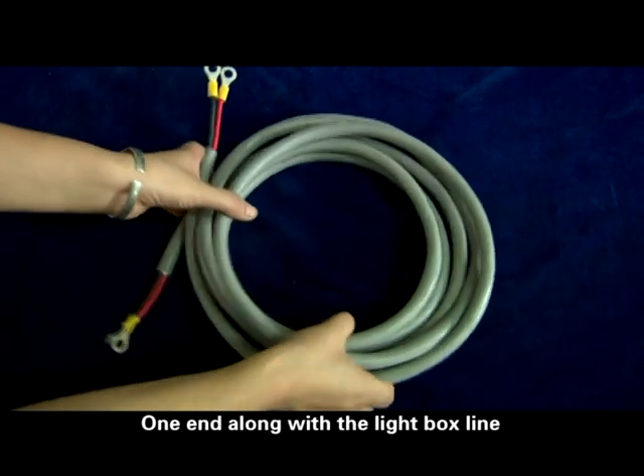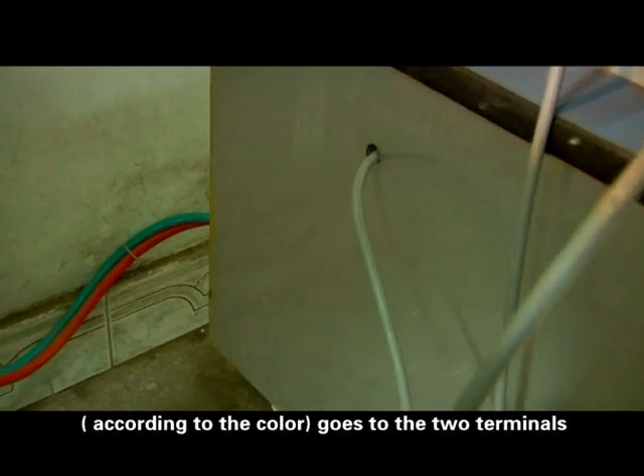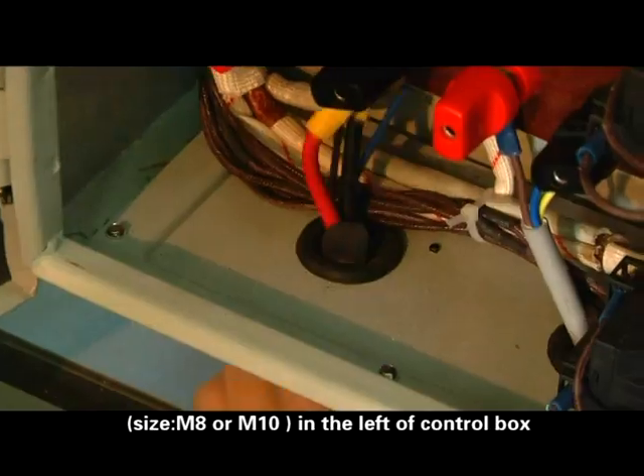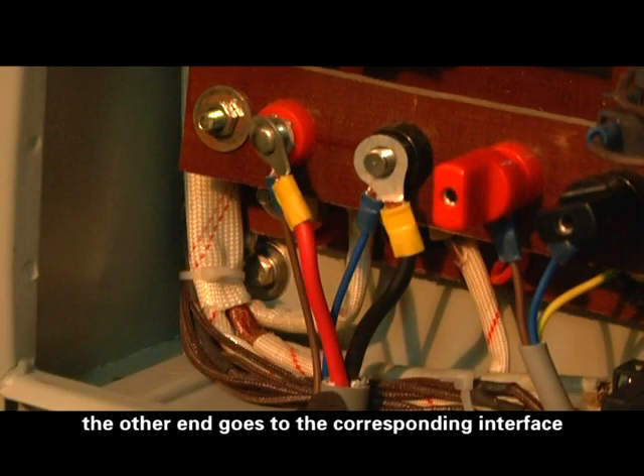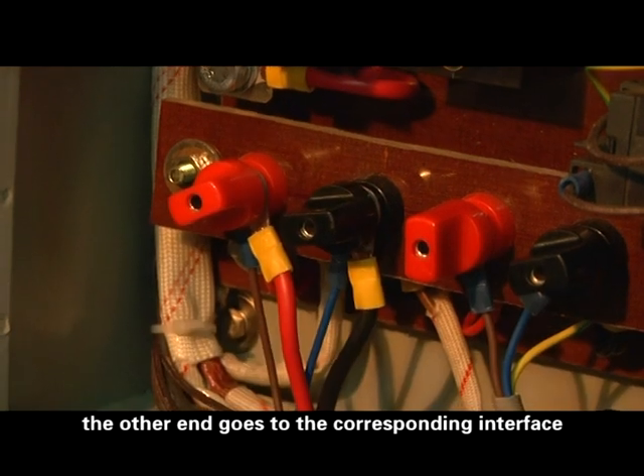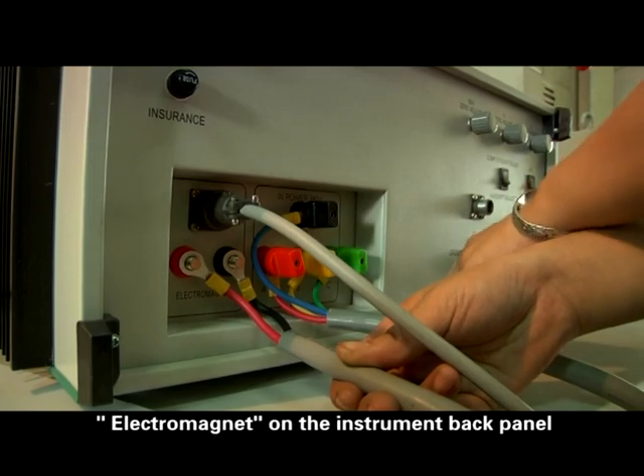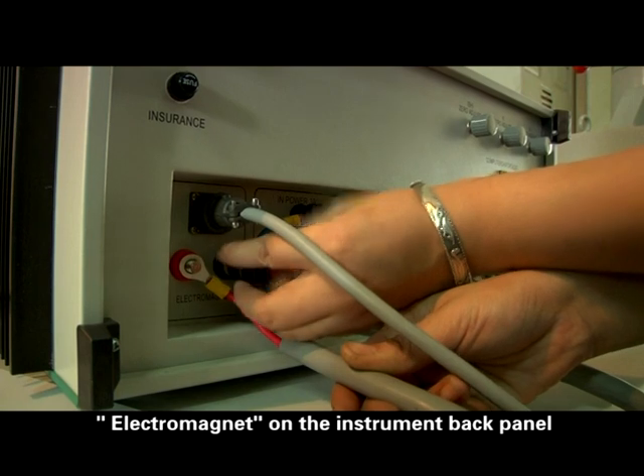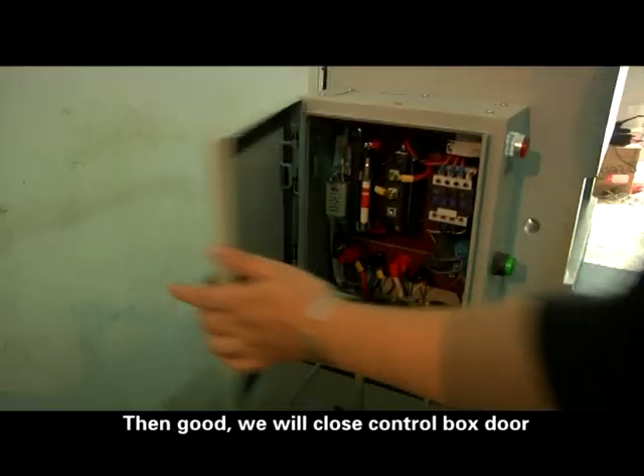Electromagnet power line. One end, along with the light box line, according to the color, goes to the 2 terminals, size M8 or M10, in the left of control box. The other end goes to the corresponding interface, electromagnet, on the instrument back panel. Then, we will close control box door.